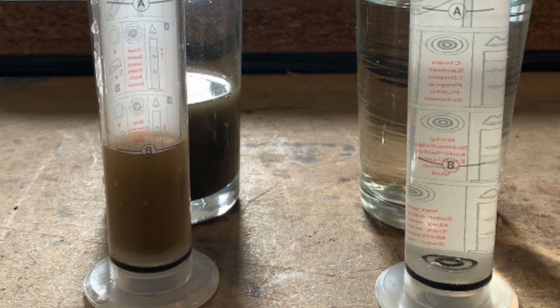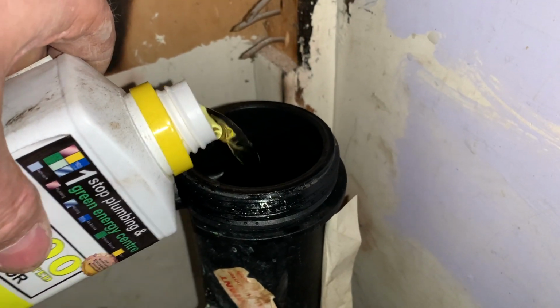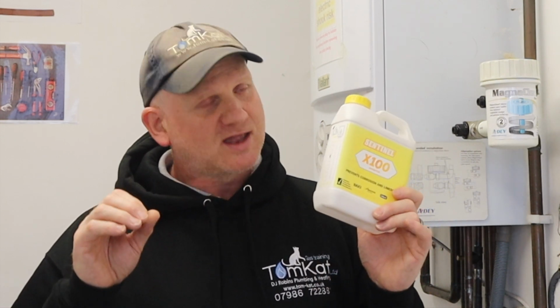So after you've had your water quality checked and your filter cleaned, make sure you add inhibitor into your system. Inhibitor will inhibit the corrosion in the system. So also in your service, make sure your engineer is putting some more inhibitor in. There are loads of test kits out there as well which will tell the engineer how much inhibitor is in the system and how much they need to put in. And again, that's going to cost more money. So again, in your asking for how much does it cost for the service, make sure they're putting some inhibitor in for you as well, because it's all going to help prolong the life of your boiler, because having the boiler replaced is a lot more expensive than having a bit of inhibitor in your system checked every year.